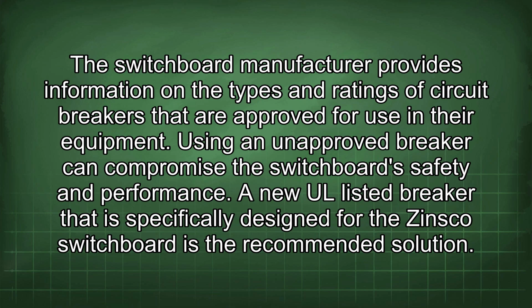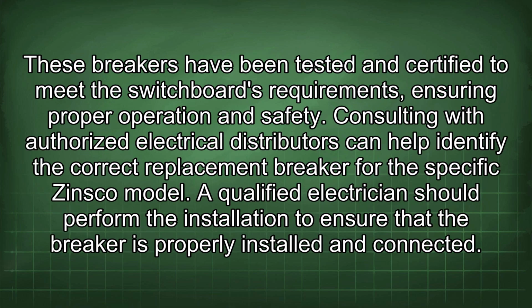A new UL-listed breaker that is specifically designed for the Zinsco switchboard is the recommended solution. These breakers have been tested and certified to meet the switchboard's requirements, ensuring proper operation and safety. Consulting with authorized electrical distributors can help identify the correct replacement breaker for the specific Zinsco model.